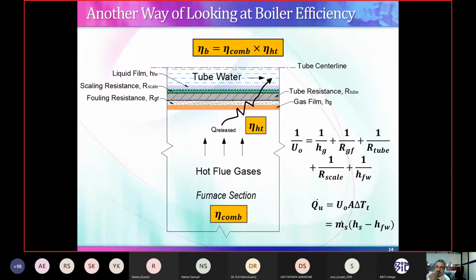Out of these resistances, what is under your control? Hg is in the control of the designer. RGF, the fouling resistance, is in our control. Tube is not under your control. It is the material requirement as per the temperature requirement of the boiler. Scale is under our control. But HFW is not in our control because it is under the control of the designer. So if I can control this fouling and scaling, my overall heat transfer coefficient will improve. This will improve my useful energy, and so improve my m dot s from the same heat transfer area. So my m dot s will increase by just controlling scaling and fouling resistances.